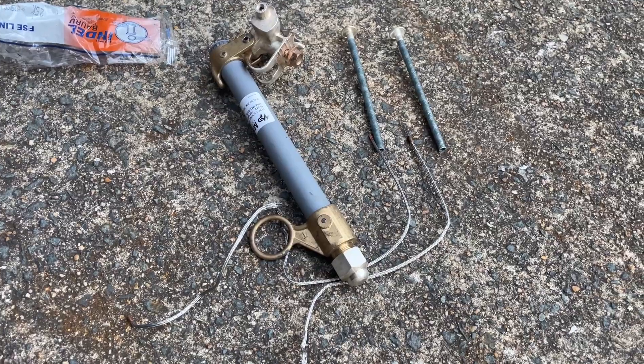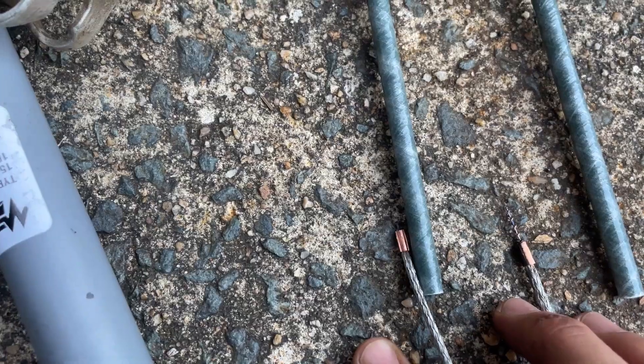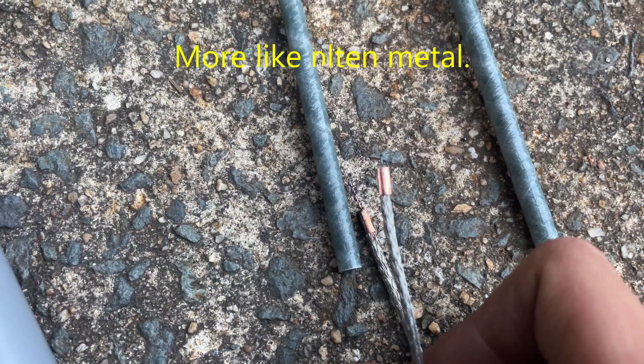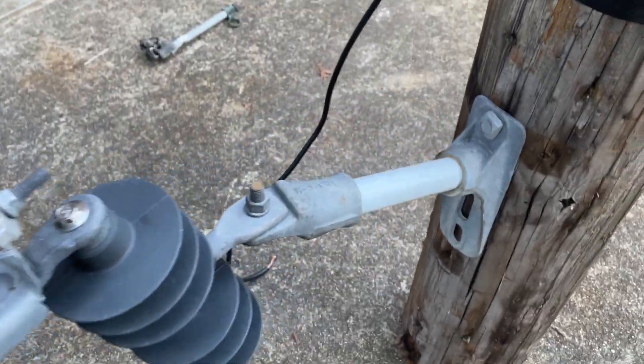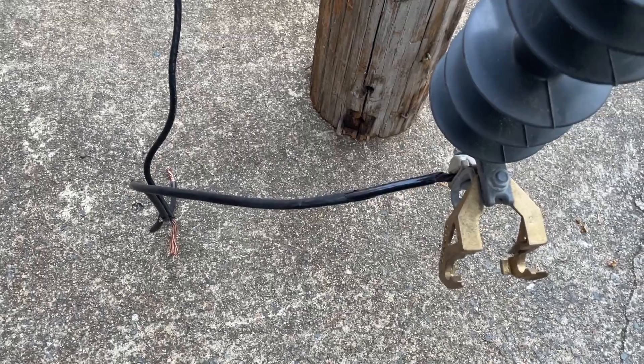That test was successful. This was the 25k fuse, this was the 1.5 D fuse. As you can see, it melted. In the slow-mos you could see a couple sparks. This is the setup: cutout, fiberglass bracket, pull wire, and another wire.